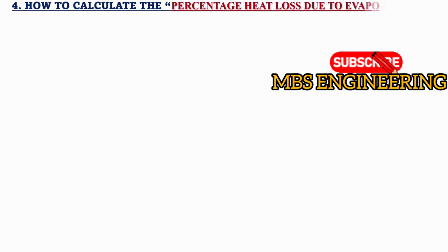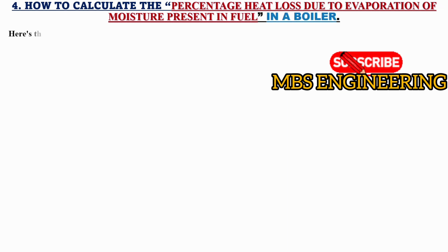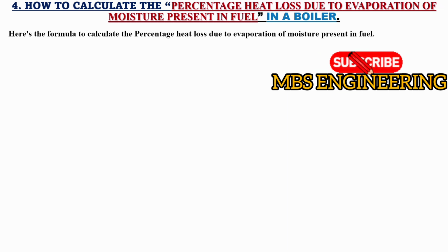Next, we will learn and understand how to calculate the percentage heat loss due to evaporation of moisture present in fuel in a boiler. Here's the formula: the percentage heat loss due to evaporation of moisture present in fuel in a boiler is equal to M multiplied by (584 plus Cp multiplied by (Tf minus Ta)), and then the obtained value is divided by GCV.